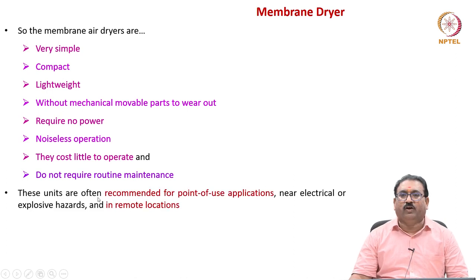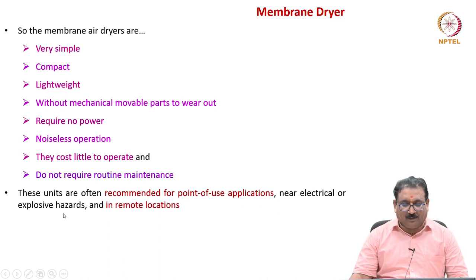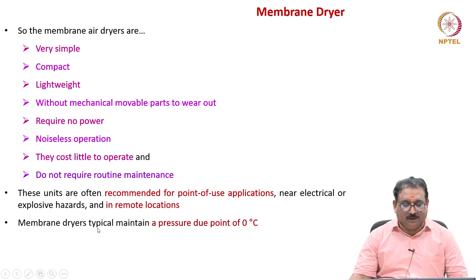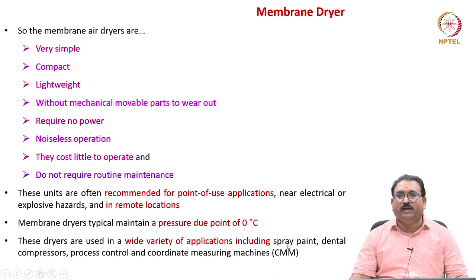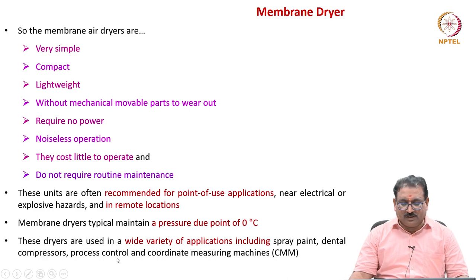These units are often recommended for point-of-use applications near electrical or explosive hazards and in remote locations. Membrane dryers typically maintain a pressure dew point of 0 degrees centigrade. These dryers are used in a wide variety of applications including spray paint, dental compressors, process control, and coordinate measuring machines.